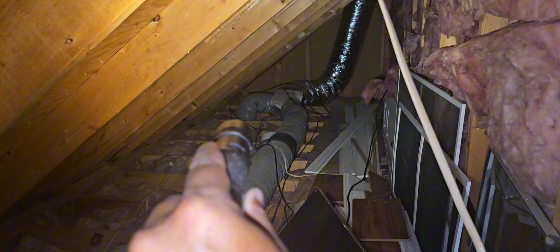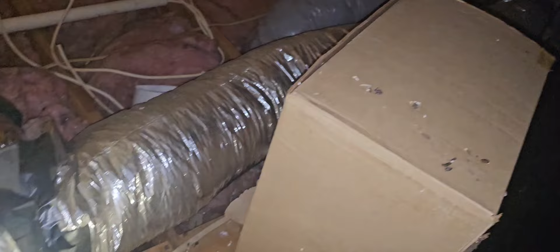Alright, just to give everybody an idea, because I'm wrapping it up here: that vent back there is getting like 400 something feet per minute of air. Feet per minute, obviously my anemometer does not calculate cubic feet, I have to do math for that, I'm not doing it right now. But that's where most of the air is coming out of. Then right here is in the kitchen, that's getting about 100 something, almost a little under 100 feet per minute. And I gotta believe these are all 6 inches, because that's a 6-inch hole. There's no way these are 8-inch flex.